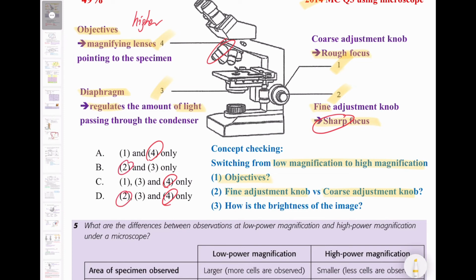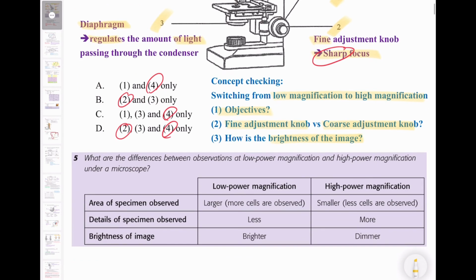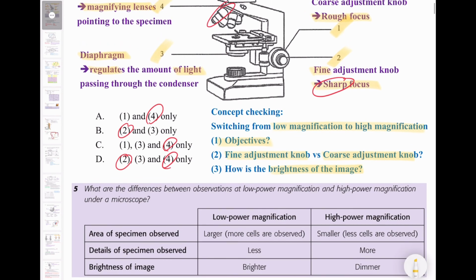The last concept is checking the brightness of the image at low magnification and high power magnification. From this table, we know that comparing low power and high power magnification, the brightness of the image is dimmer at high power magnification. So that's why we need to adjust the diaphragm to increase the light intensity passing through the condenser. That's why number 3 is also included.